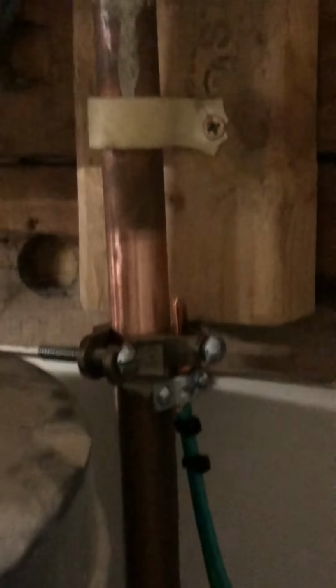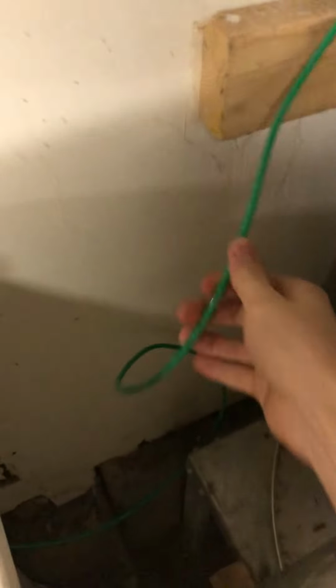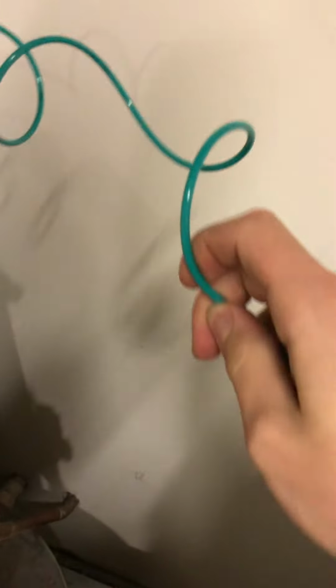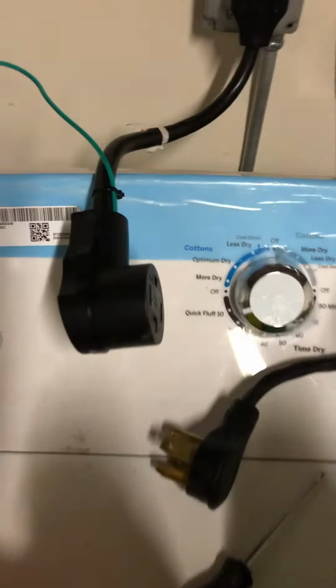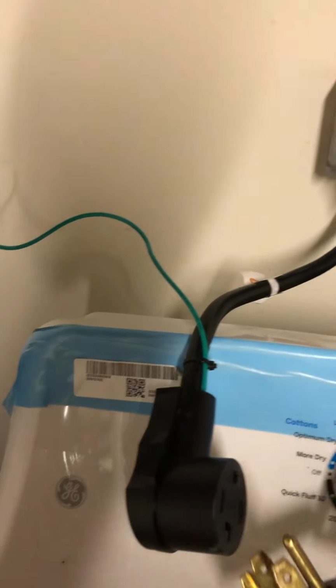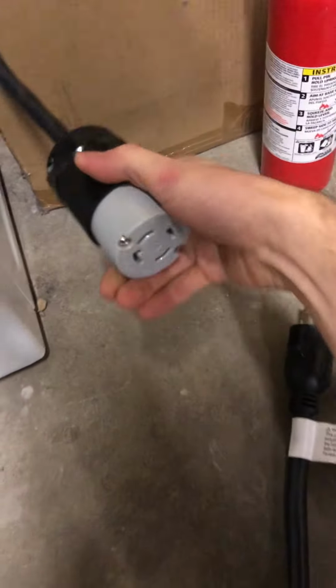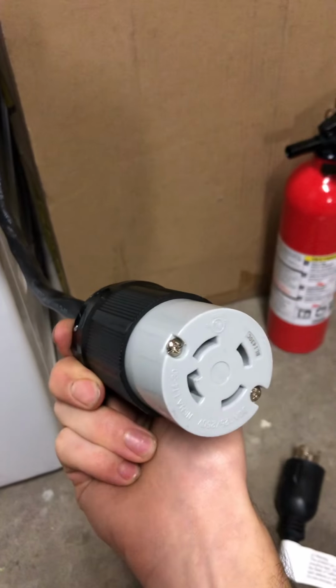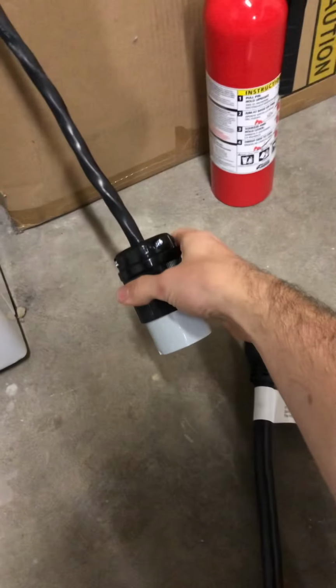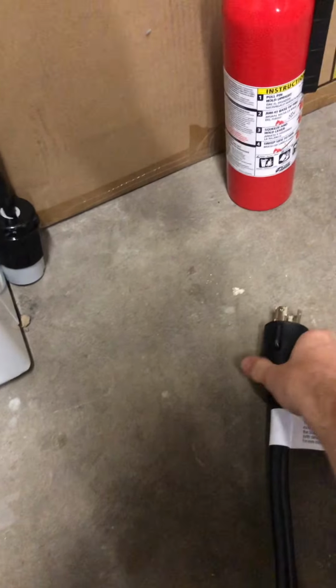a ground clamp on the cold water pipe, the water heater here. And I've got 8 gauge wire, so that should be good for 30 amps. But I have a feeling that this is not 8 gauge. I think it actually is going to be 10 gauge, so I'm not totally safe, but I'm doing the best I can. So yeah, again, we got 3-prong to 4-prong splitter, and then that cable just goes to a twist lock. This is a NEMA L14-30, which is again a 250 volt 30 amp circuit.